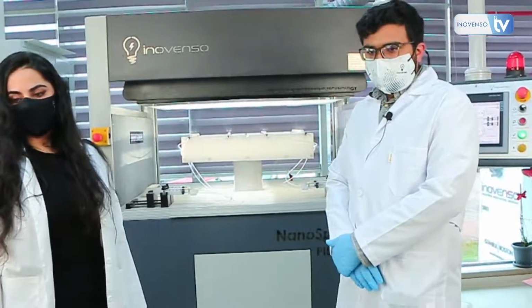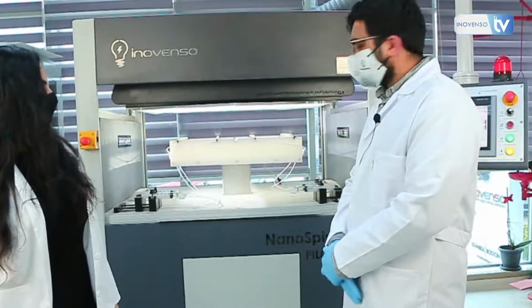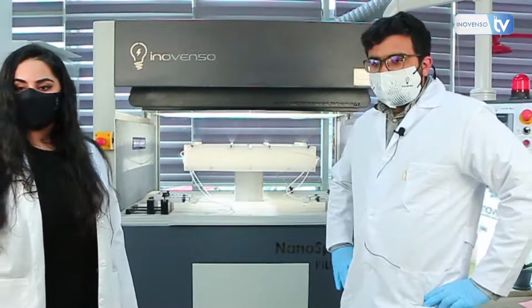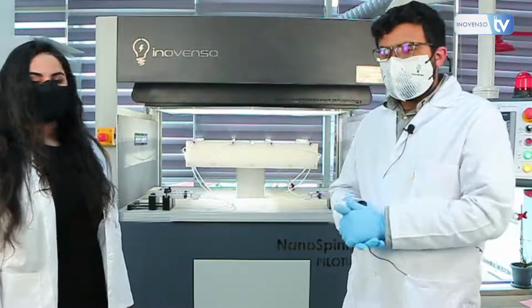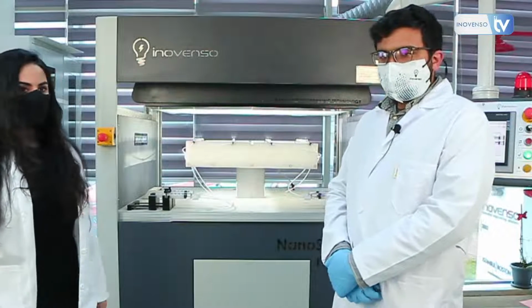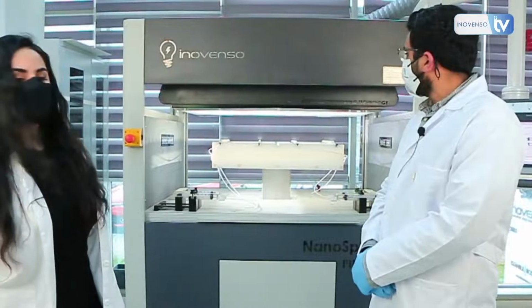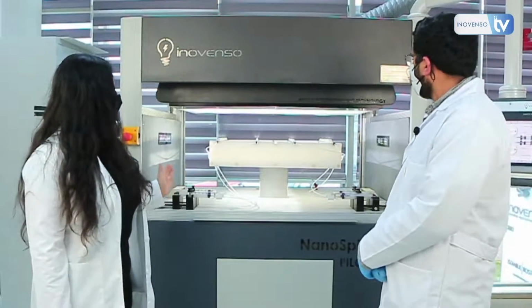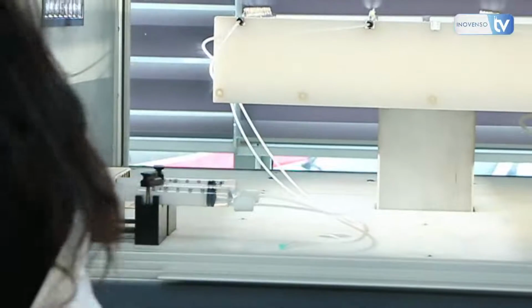So we have another question, Amar. How will it work on highly volatile solvents? Well, you can use volatile solvents up to a certain ratio, and it should work. Regarding the previous question on volatile solutions, up to let's say 35% acetone, it should be operational on our machine. As we have previously mentioned, we have four different adjustable syringe pumps here, and you can use four different solutions and control all of them on our touch panel screen.